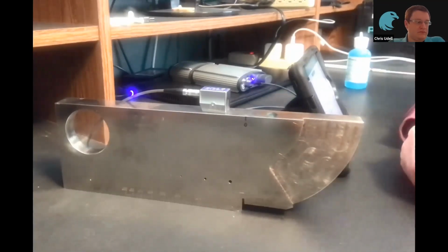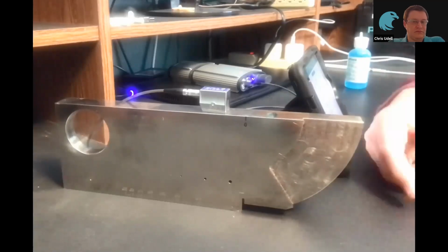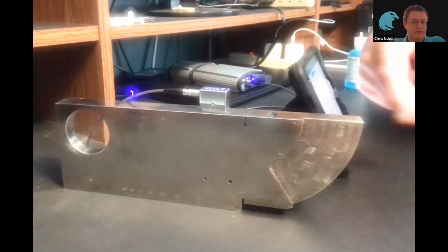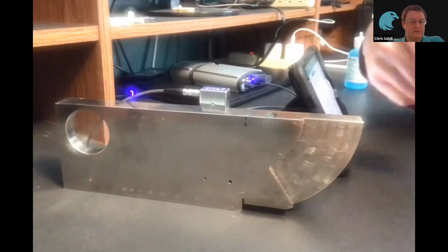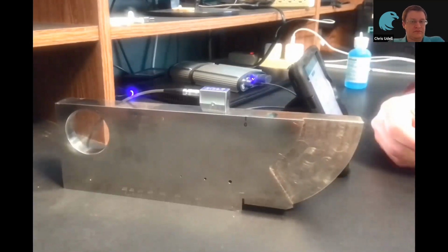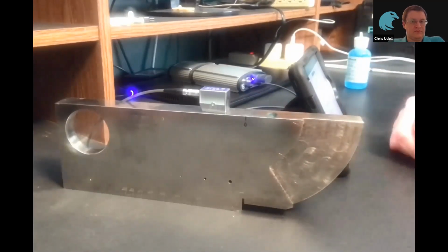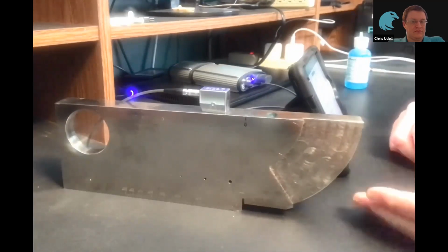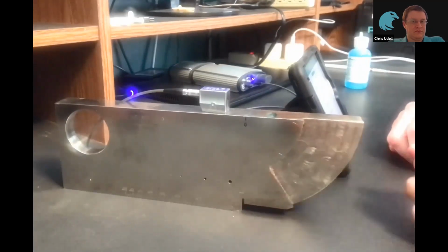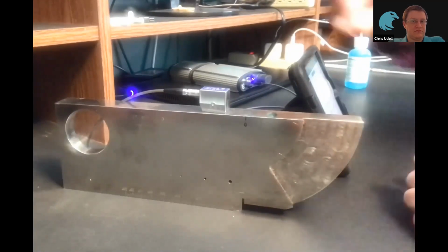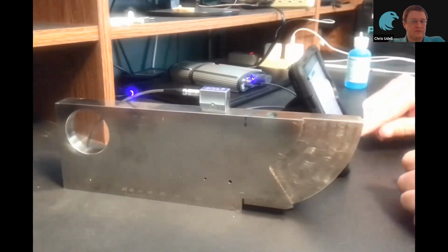So since it's constantly doing this, if we go over top of an indication and we can't reproduce it, we can hit record and still know that we've captured that peak. To demonstrate this, I'll show you on a standard IIW type 2 block where we have a 2-inch radius and a 4-inch radius, and we'll use a regular shear wave transducer.